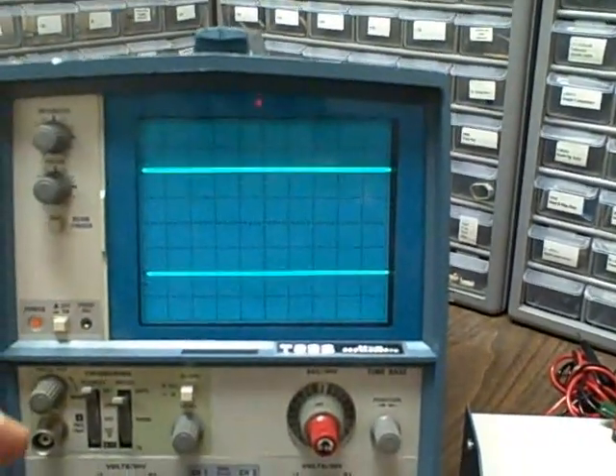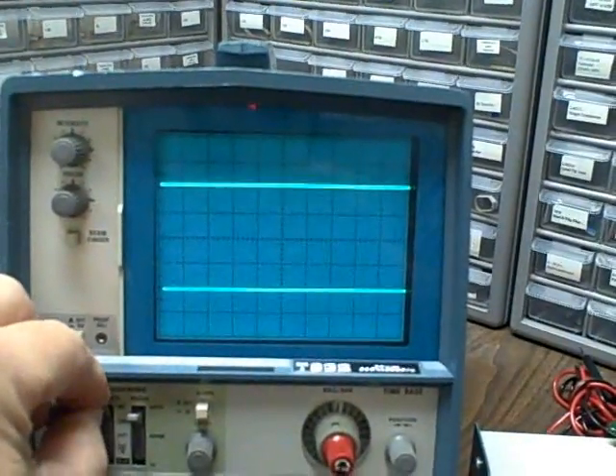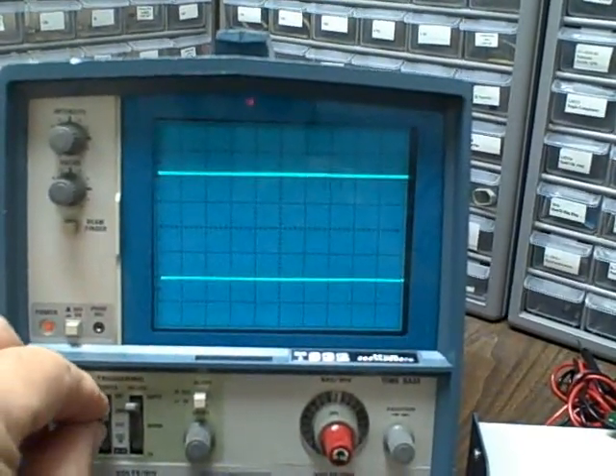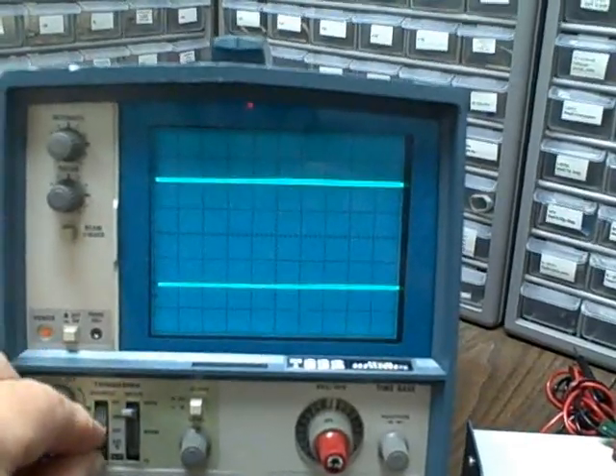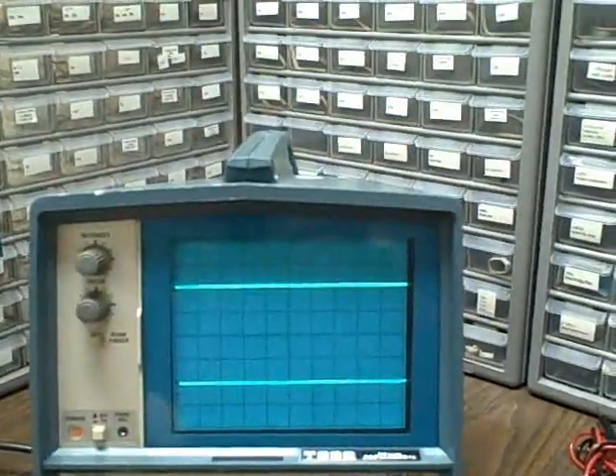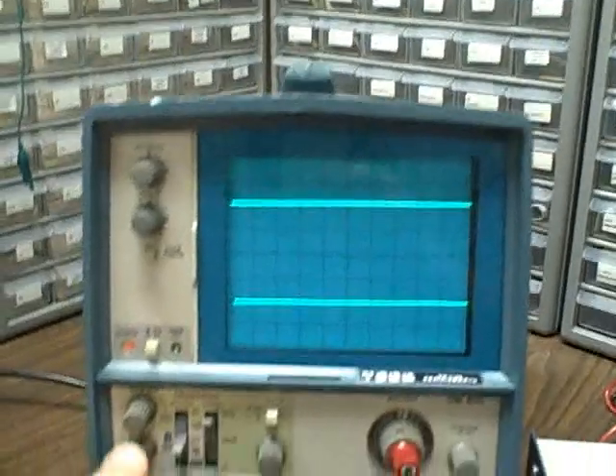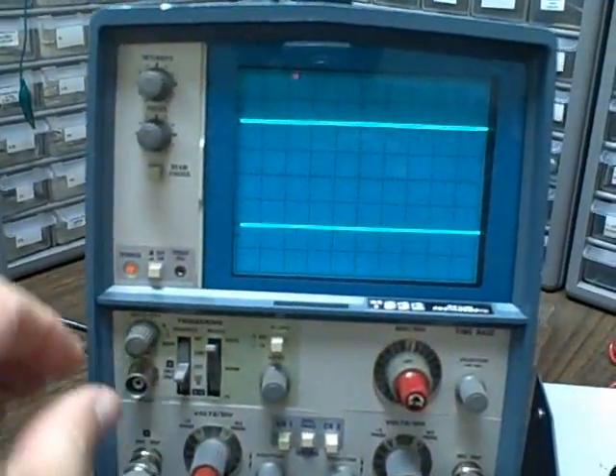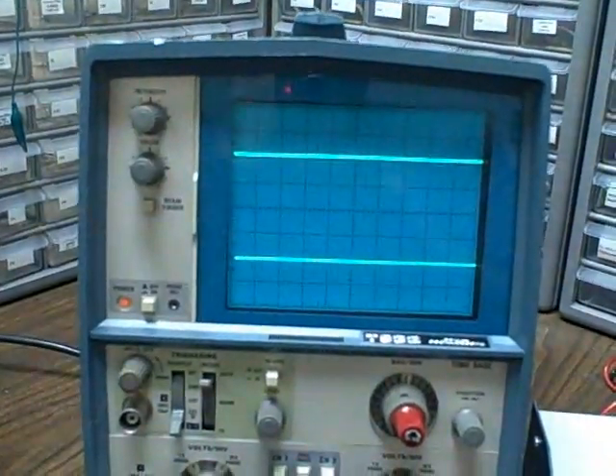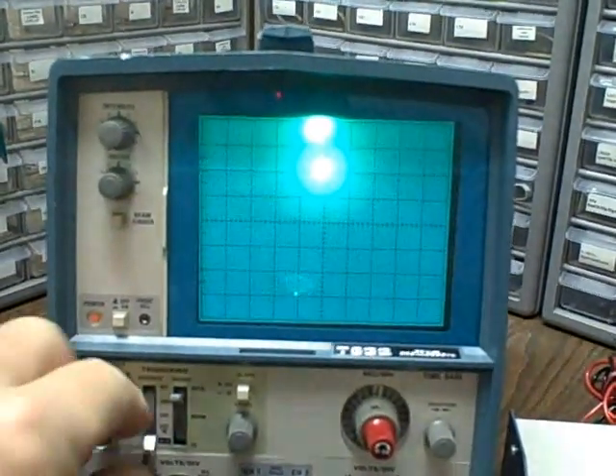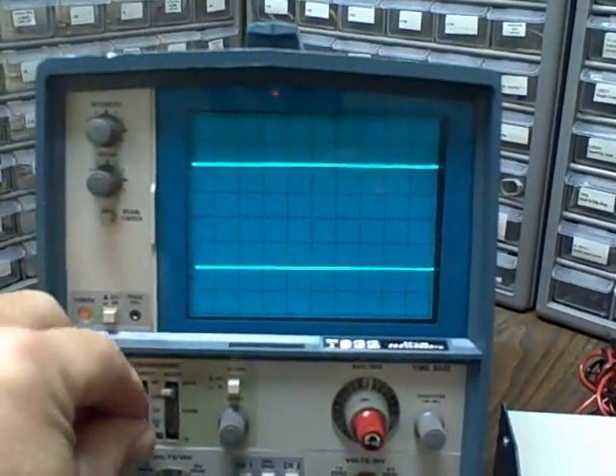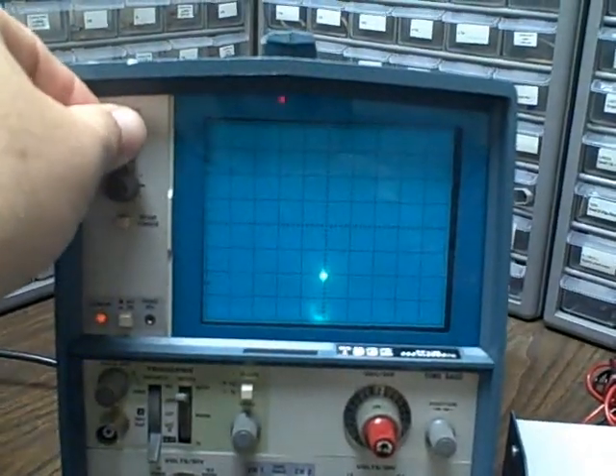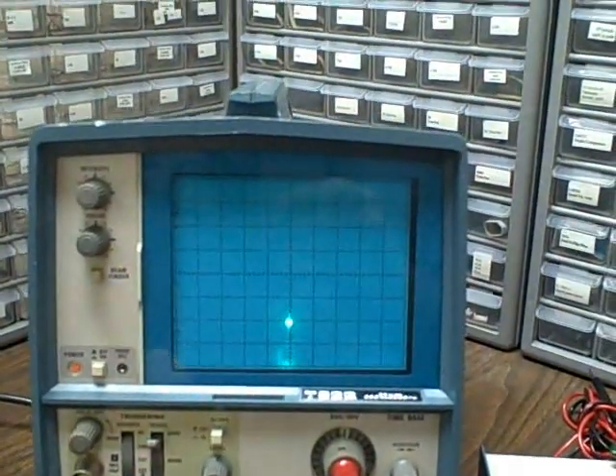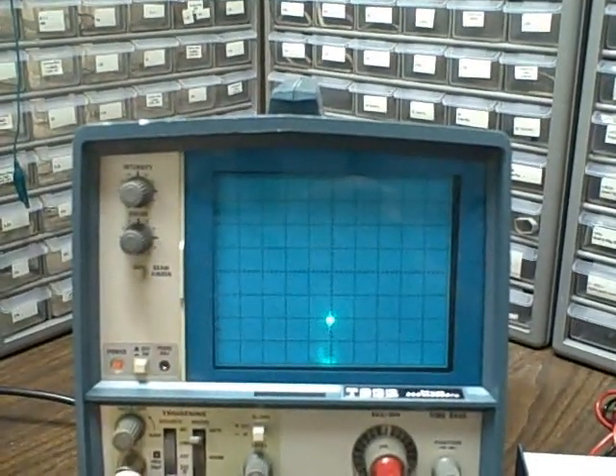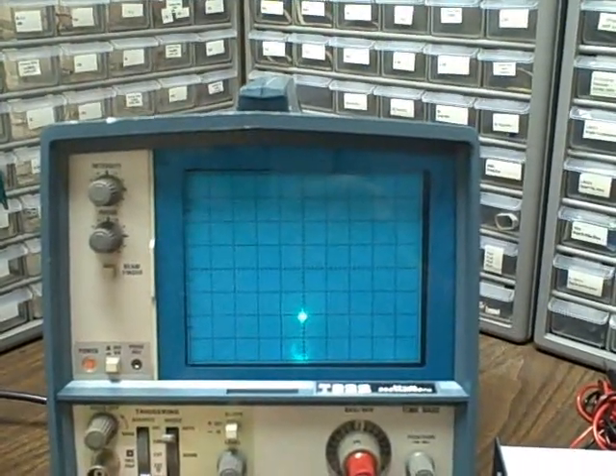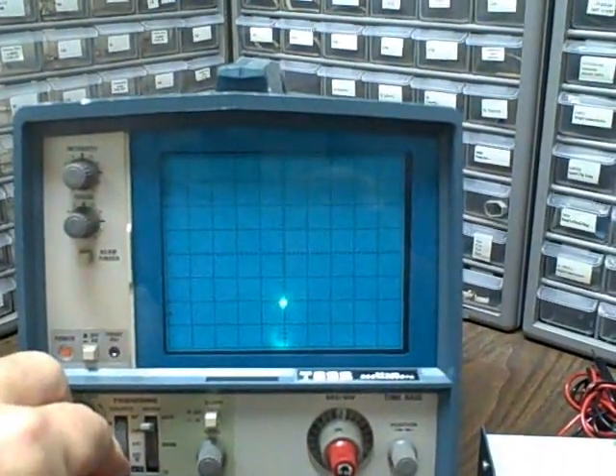And we have internal triggering, line triggering where we're running off the 60 hertz, external triggering where the external trigger point is right at this location, and then external divided by 10, and then finally the XY input. The X input would be at this point, and the Y input would be on the channel 1.